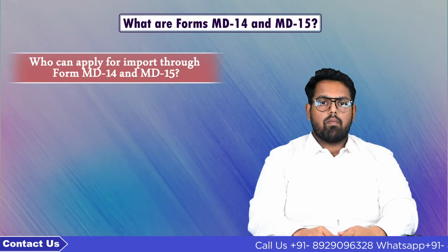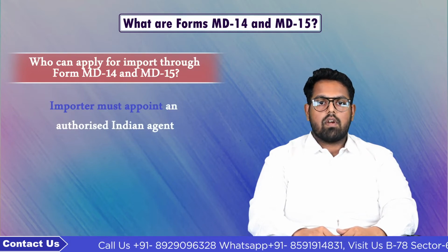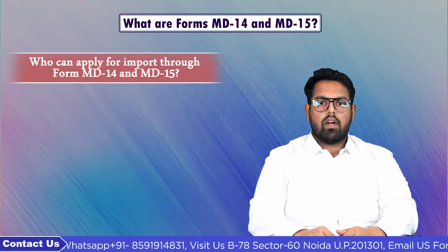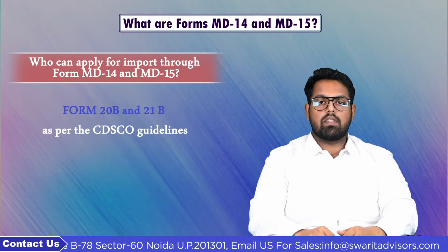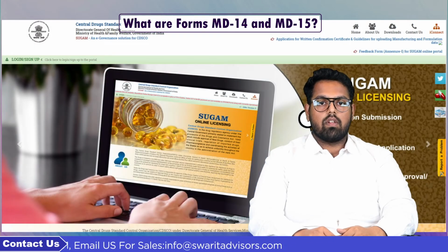Who can apply for import through Form MD-14 and MD-15? The importer must appoint an authorized Indian agent. The agent must possess a manufacturing or wholesale license in Form 20B and 21B as per the CDSCO guidelines. The agent shall then apply for the license through the Sugam portal online.